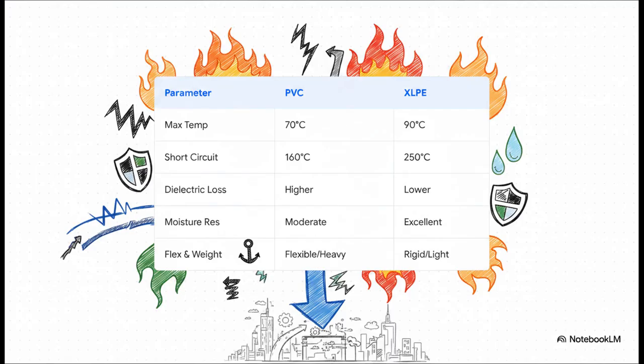Okay, looking at the numbers here, notice how XLPE absolutely dominates when it comes to thermal limits and environmental resilience. It's got a higher max operating temperature, a vastly higher short circuit threshold, much lower dielectric loss, and excellent moisture resistance. But take a look at that bottom row. This is where PVC really shines, because it is highly flexible, whereas XLPE, while lighter, is considerably more rigid. So let's unpack how that actually translates into real-world performance differences.